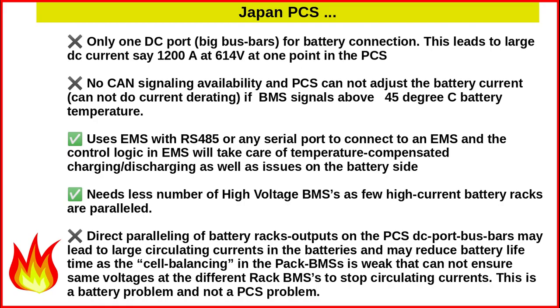Now, the last point, which is not good, is that direct paralleling of battery rack outputs on the PCS DC port bus bars may lead to large circulating currents in the batteries and may reduce the battery life, as the cell balancing in the pack BMSs is generally weak, that cannot ensure the same voltages at the different rack BMSs to stop the circulating currents. This is a battery problem and not a PCS problem, and this battery problem is there for both Japan PCS as well as for China PCS.